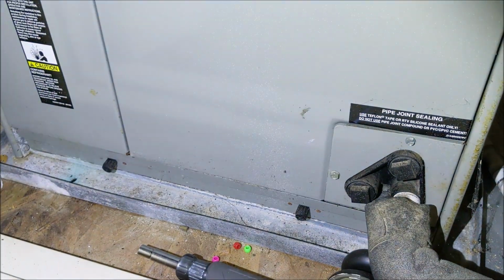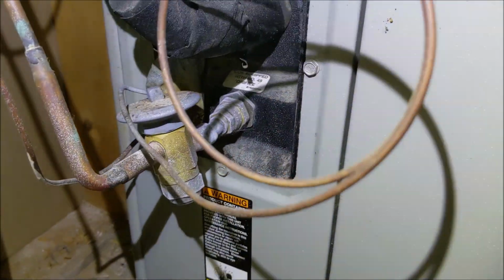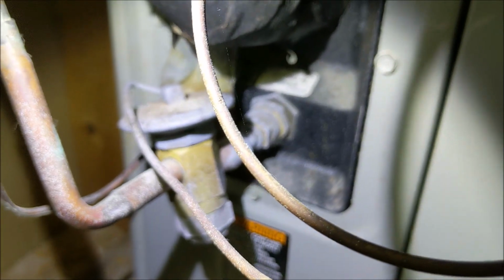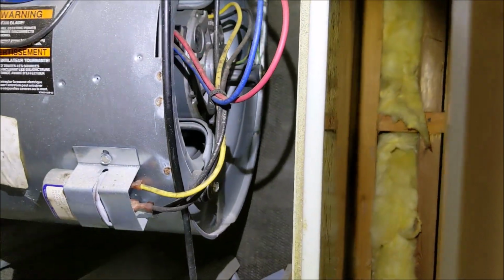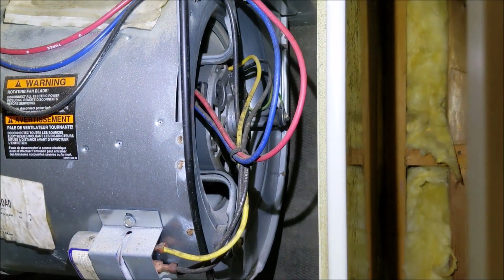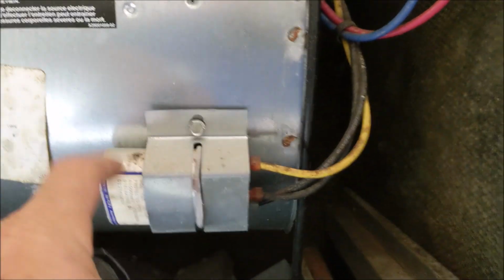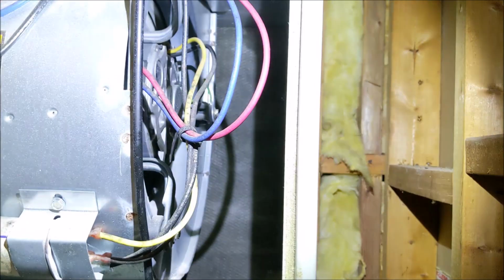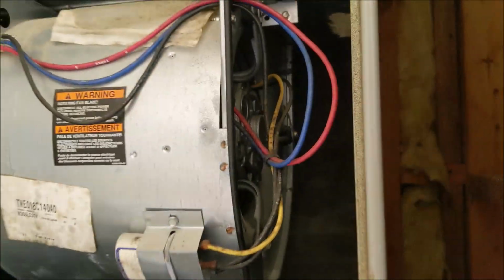So we got the electric air handling unit here in the attic, in the laundry room. As you can see, we're starting to ice up here because the blower motor is not coming on. As you can see, it's spinning. That's because I forced it. Most of the time these capacitors will go out and cause the blower not to come on. Right now this is the one that controls the garage.